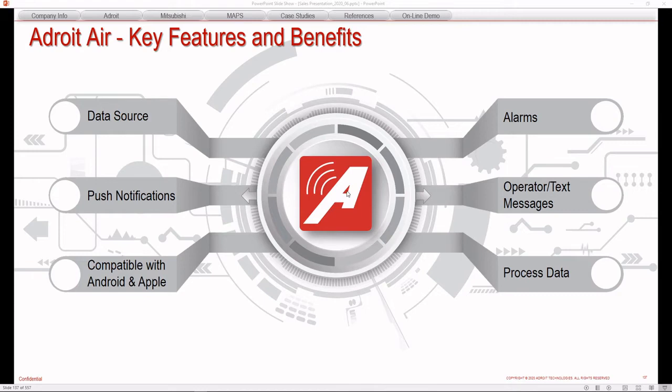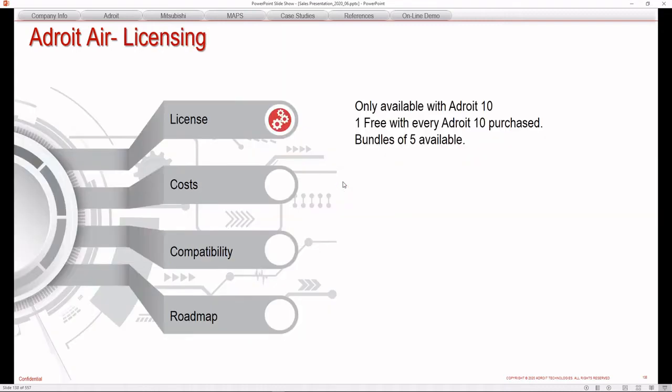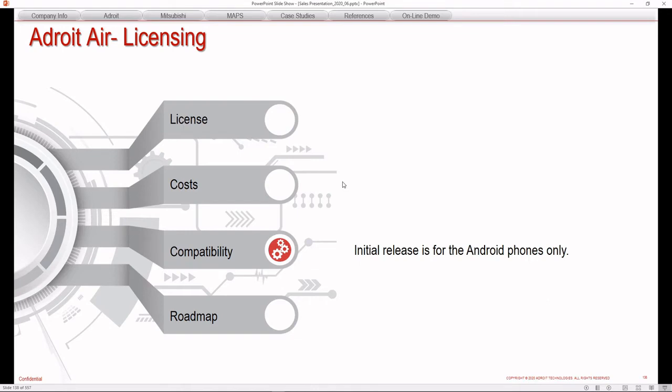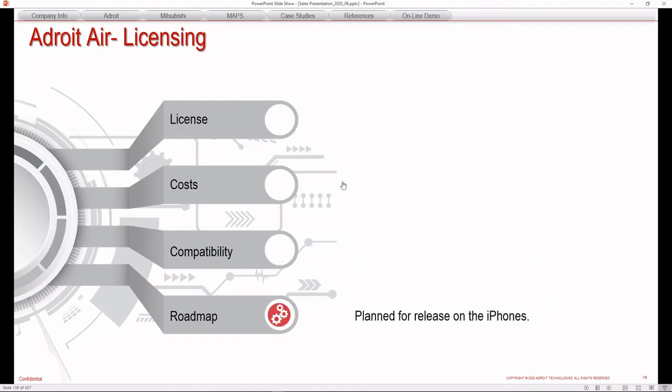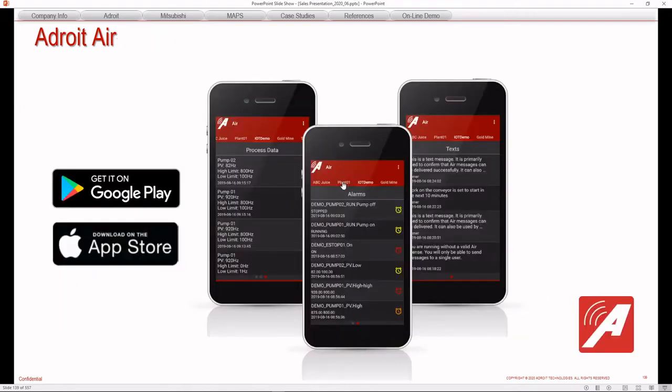Each user is mapped to a single alarm list or alarm agent to ensure that they only receive alarms relevant to them. The app user will see a list of up to 20 of the highest priority active alarms. Alarm priorities can be used to filter out less important alarms. The operator can also send customized user text messages. App users will be able to view a history of up to the last 20 messages delivered to them.